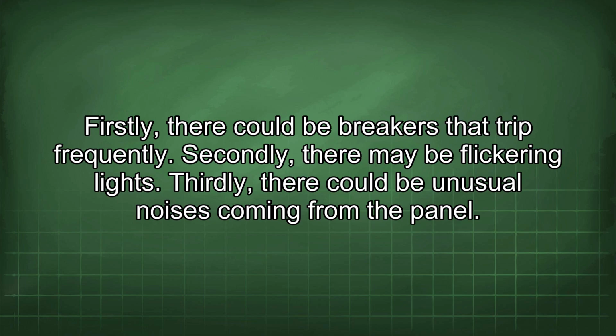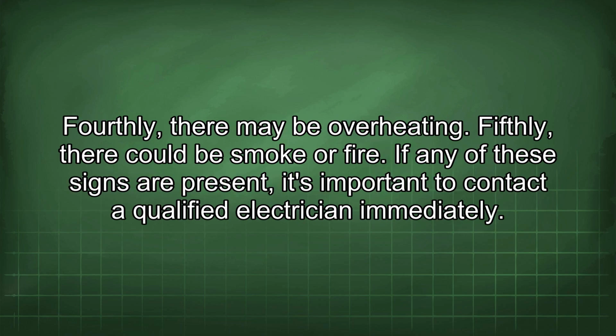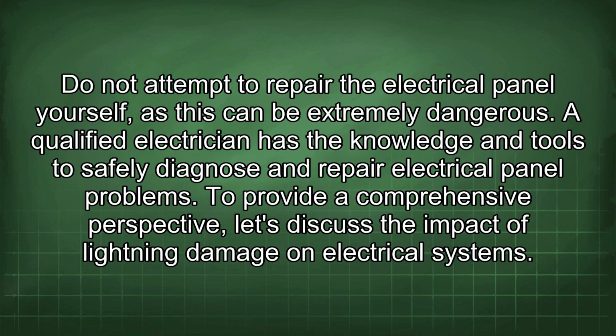Firstly, there could be breakers that trip frequently. Secondly, there may be flickering lights. Thirdly, there could be unusual noises coming from the panel. Fourthly, there may be overheating. Fifthly, there could be smoke or fire. If any of these signs are present, it's important to contact a qualified electrician immediately. Do not attempt to repair the electrical panel yourself, as this can be extremely dangerous. A qualified electrician has the knowledge and tools to safely diagnose and repair electrical panel problems.